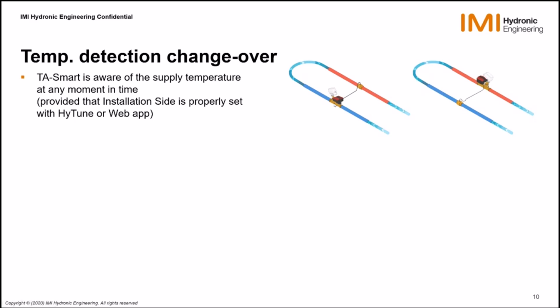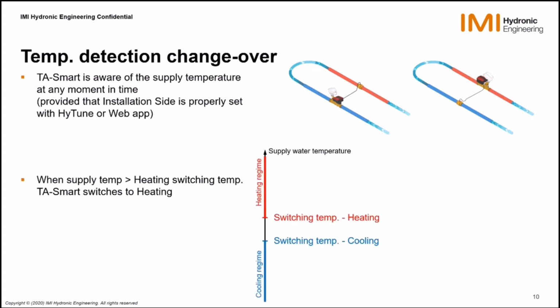Then, depending on whether the supply is colder than the return or warmer than the return, we are able to detect whether we are in heating or in cooling. Actually, we are not going to do temperature detection by looking at the difference between the supply and the return, because the flow could be quite small, and therefore the two temperatures could be very, very close, if not equal. So what we are doing is providing a system by which TA-Smart monitors the supply temperature, and if the supply temperature is above a heating switching temperature, then TA-Smart considers it is in heating and will assign to itself the max flow of heating.